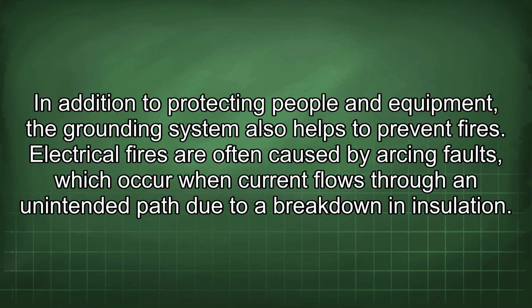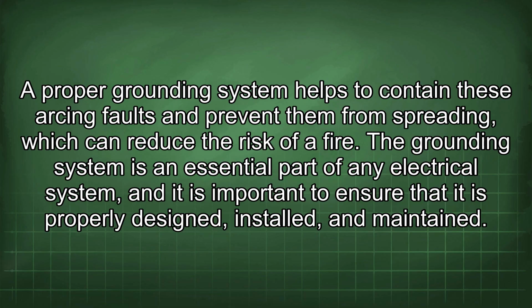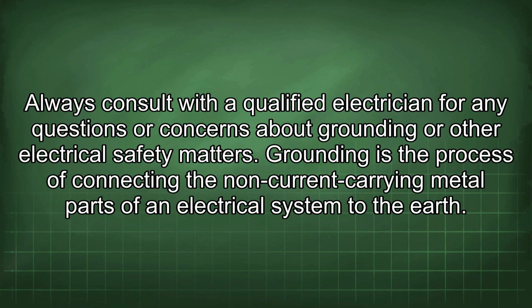In addition to protecting people and equipment, the grounding system also helps to prevent fires. Electrical fires are often caused by arcing faults, which occur when current flows through an unintended path due to a breakdown in insulation. A proper grounding system helps to contain these arcing faults and prevent them from spreading, which can reduce the risk of a fire. The grounding system is an essential part of any electrical system, and it is important to ensure that it is properly designed, installed, and maintained. Always consult with a qualified electrician for any questions or concerns about grounding or other electrical safety matters.